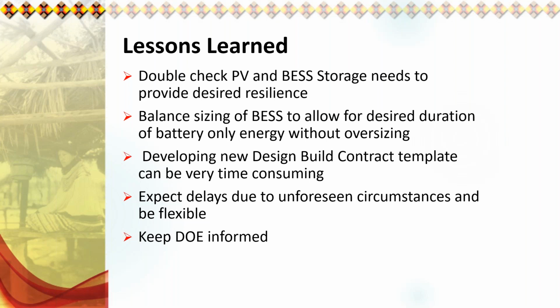The other thing we needed to look at was balancing the sizing of the BESS to allow for the desired duration of battery-only energy without oversizing. This is important because theoretically you could put enough batteries out there to run the facility for 2 weeks, but does that really make practical sense? You're just not going to be using the energy, and it's not going to be recycling through the battery energy storage system. So the idea with the 3 to 4 hour duration for the BESS running the facility is to give it the opportunity to power recycle, to discharge and recharge.